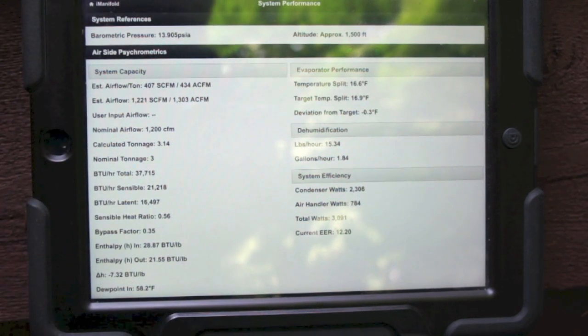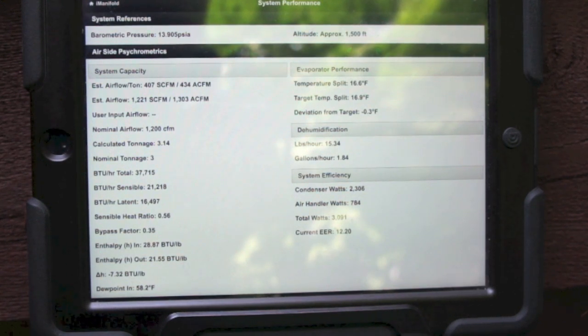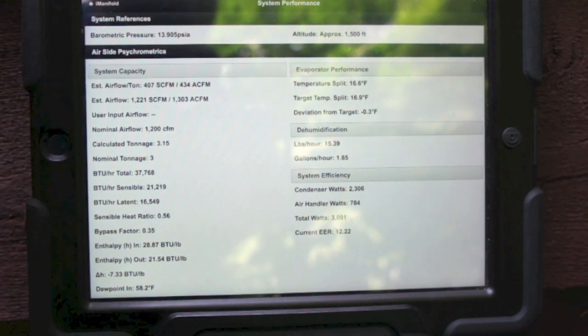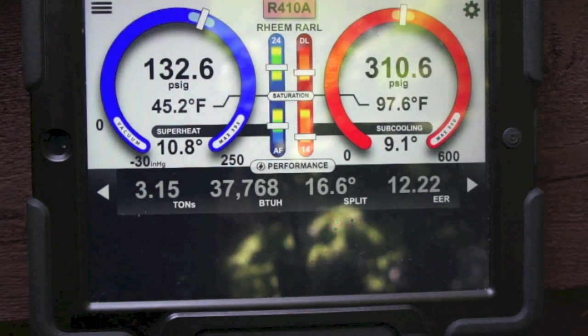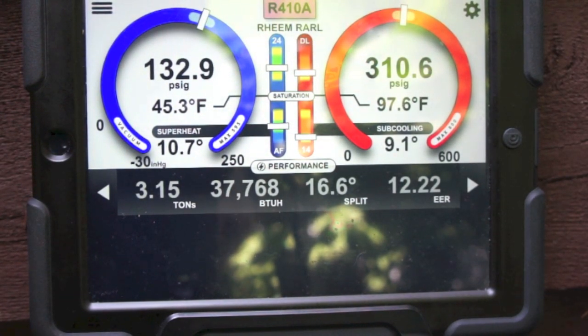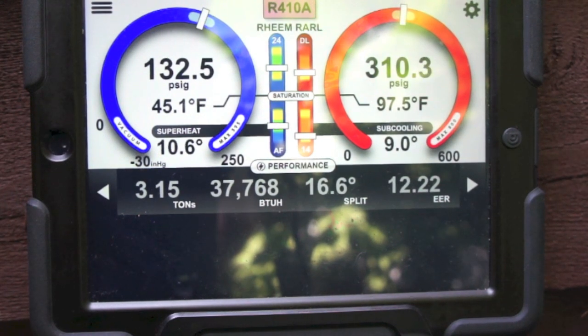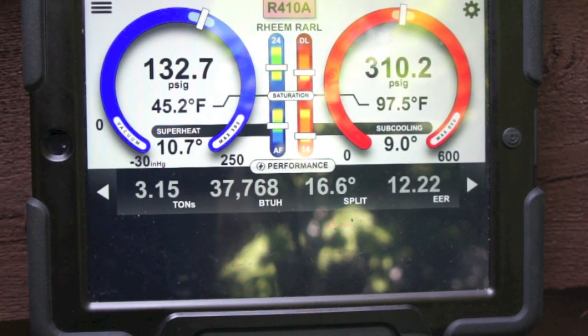We're at 37,715 BTUs total, 21,000 sensible, 16,000 latent, a sensible heat ratio of 0.56, bypass factor of 0.35. You can see our change in enthalpy is 7.30, and you can see obviously our condenser watts and our EER run about 12.20. So literally in seconds, and the time that it took for the system to settle out, and the time it took to get our electrical measurements, we have total system performance now with the iManifold and 2 wireless probes. This pretty much eliminates the need to make an actual airflow measurement unless it's a requirement for your job.